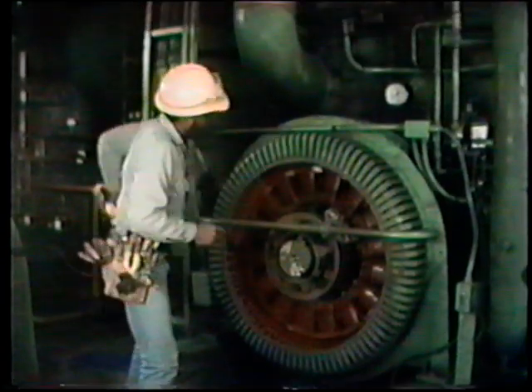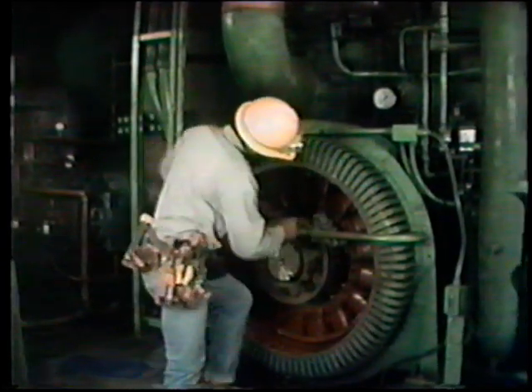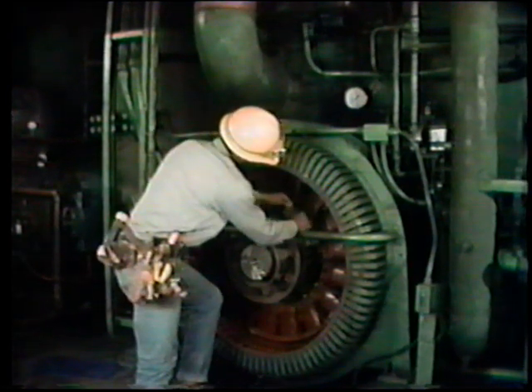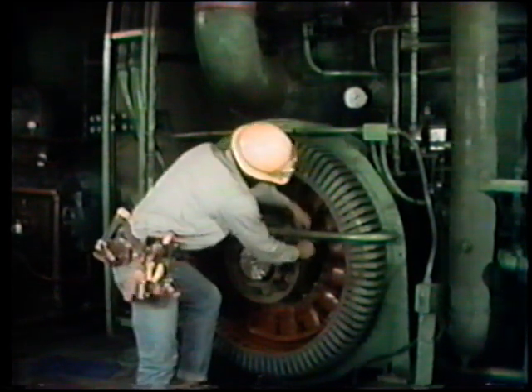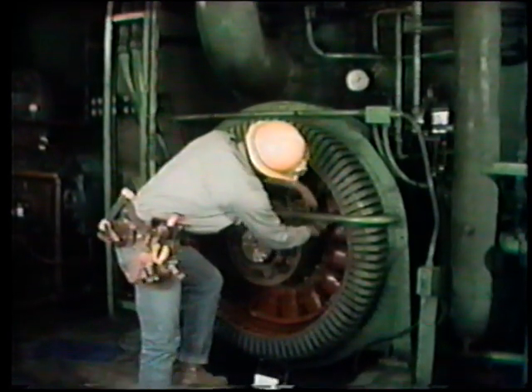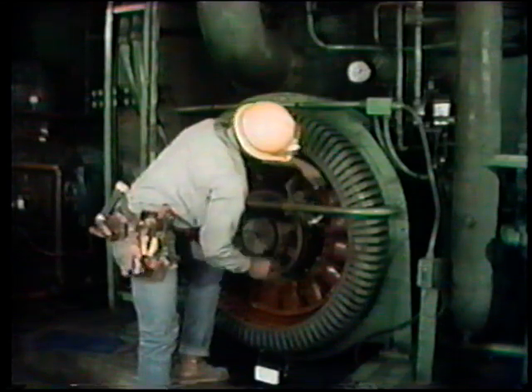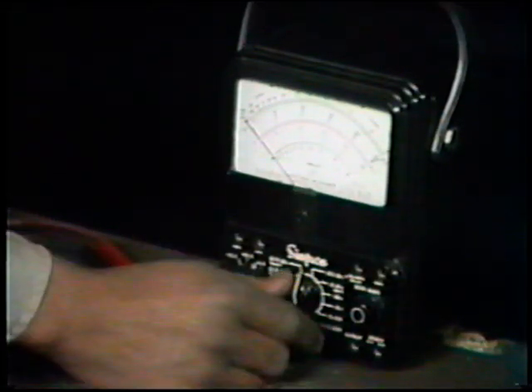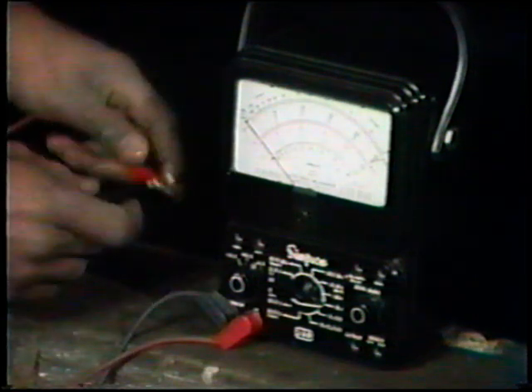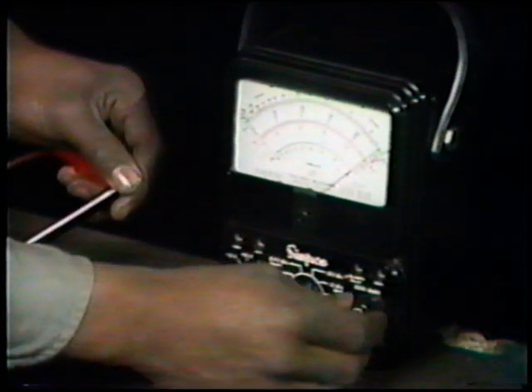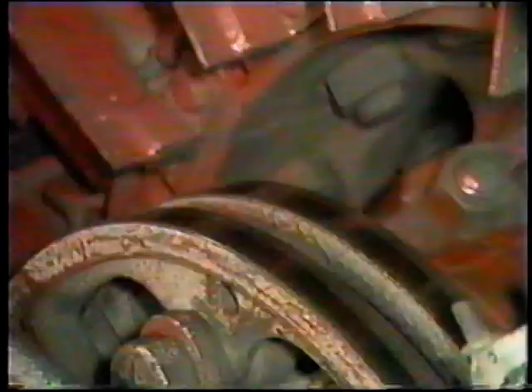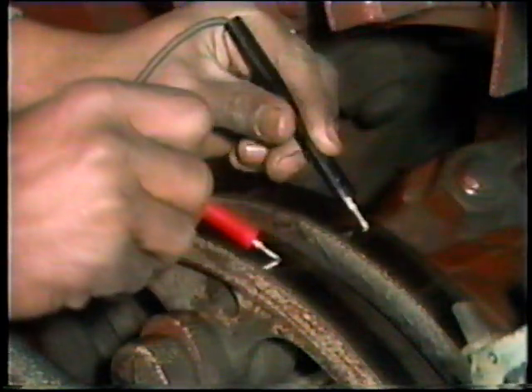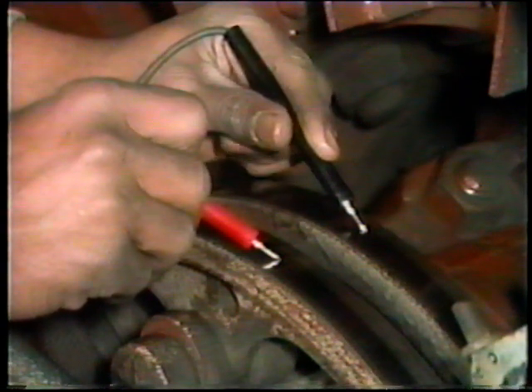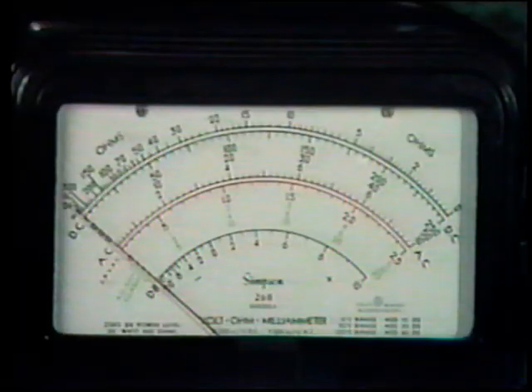Let's take a look at an example of testing a rotor for opens and shorts. To test the rotor for these problems, the rotor must first be isolated from its DC power supply. This is done by lifting the brushes from the rotor. Then a multimeter is used to measure the resistance through the rotor circuit. Before testing the circuit, the multimeter is set to the proper resistance scale and zeroed. The multimeter test probes are then placed on the slip rings, one on each slip ring, and a resistance reading is taken. The reading here is infinite resistance. This high resistance reading indicates that the rotor has an open.